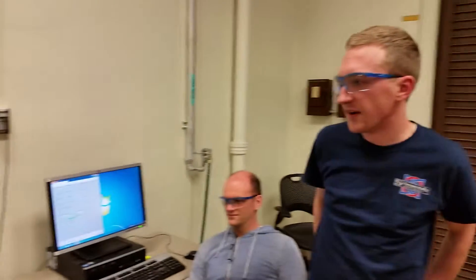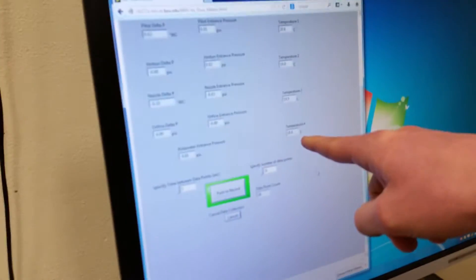And that takes about 20 minutes? Yeah, about 20 minutes. About 20 minutes between tests if you're going up about 50 standard cubic feet per minute to get to that steady state value. How much does the temperature change? So for the lower flow rates, it's about 35 degrees down here at the end. And then for the higher flow rates, it'll be at about 45 degrees. And so you can just kind of measure that by this is thermocouple number four. And you'll see on the screen right here temperature four. So if you just watch that number until it's staying pretty much the same.